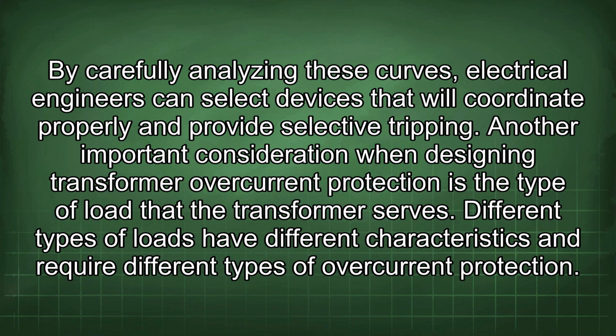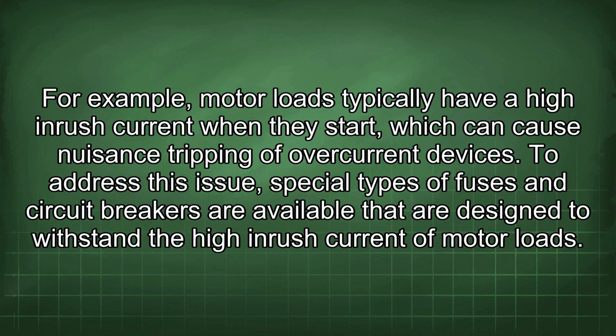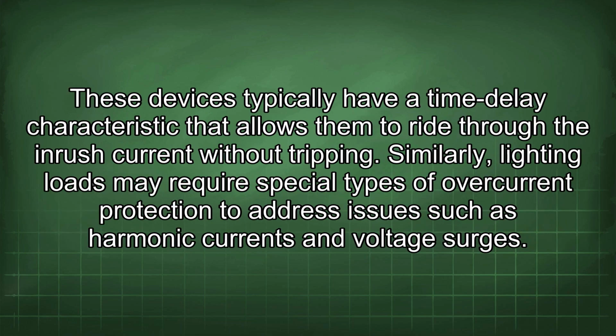Another important consideration when designing transformer overcurrent protection is the type of load that the transformer serves. Different types of loads have different characteristics and require different types of overcurrent protection. For example, motor loads typically have a high inrush current when they start, which can cause nuisance tripping of overcurrent devices. To address this issue, special types of fuses and circuit breakers are available that are designed to withstand the high inrush current of motor loads. These devices typically have a time delay characteristic that allows them to ride through the inrush current without tripping.